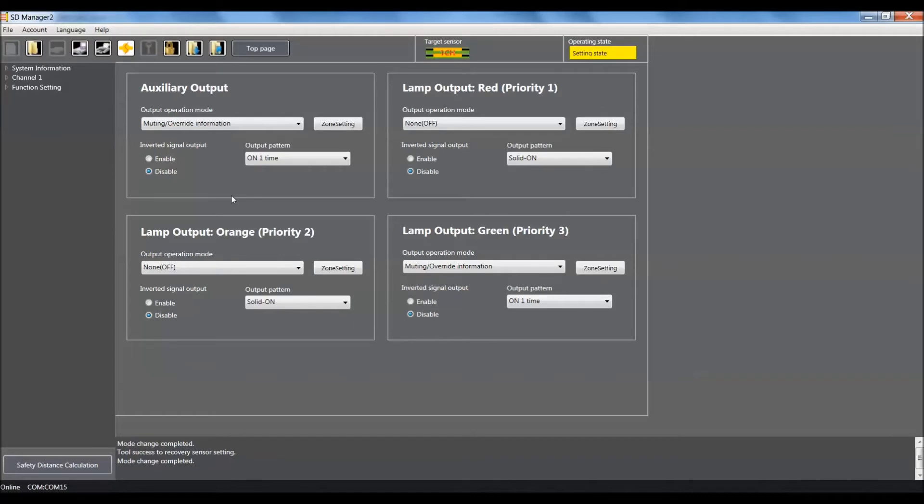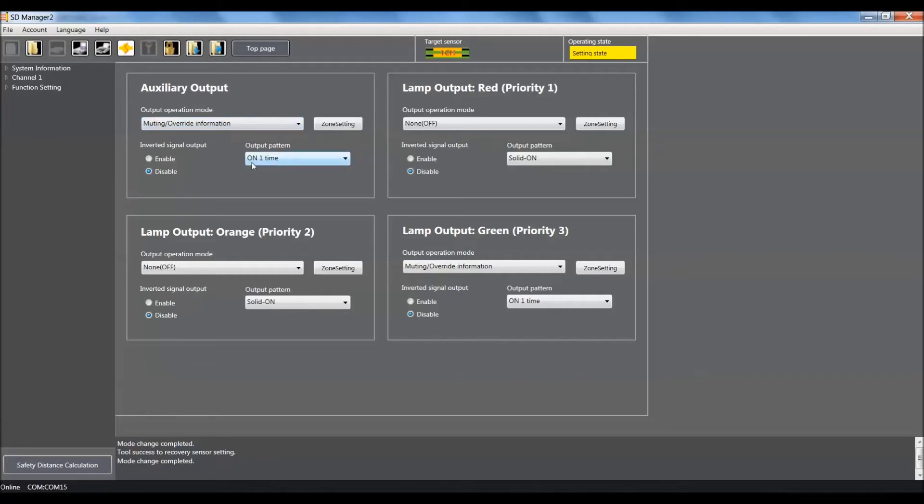If you're not sure if you have the older firmware in your global light curtain, it's good just to verify this because we will download all this to the light curtain when we're ready. For the auxiliary output, we need to make sure that muting override information is selected. We want to make sure disable is selected and on one time.